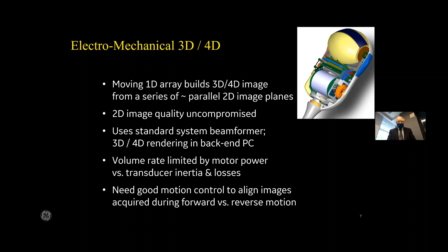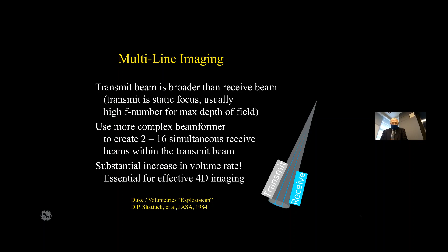So how do you get around some of these things? One way is by being a little more clever in your beamforming. Here the idea is that the transmit beam is a little broader than the receive beam, so you can fire 1 transmit beam and then get multiple receive beams coming back from that. How well can you do that? It varies, but 2 is nice. 2 for the price of 1 is not a bad thing. You can get 16, maybe even a little bit more. So that's a substantial way to increase the volume imaging rate, and the fundamental basis behind all of the electronic 4D imaging.